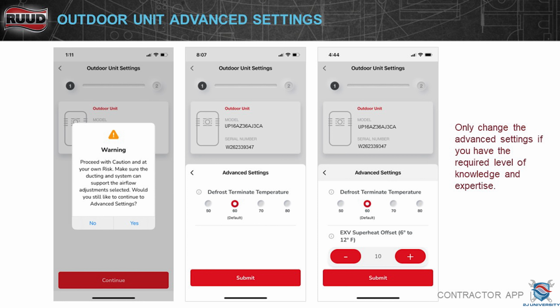Defrost termination on your outdoor unit is all set up through the Bluetooth app. There's no pins or plugs or anything like that. Like on the old style boards, they had those little pins that you could change. Those are all gone. Your old style board still has that on your base tier or builder tier stuff, but everything 15 SEER AC or higher or 16 heat pump or higher is going to be all through the Bluetooth app.